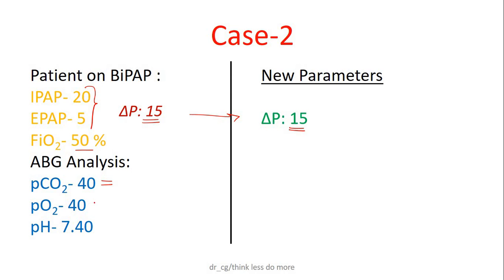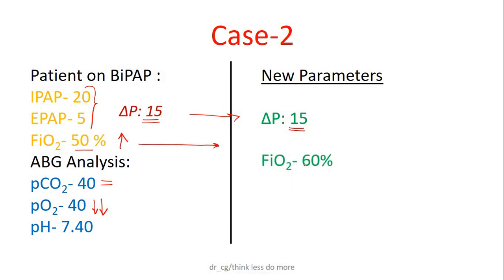Now see PO2 level — here it is 40, meaning it is very low. So we can increase our FiO2 to 60% from 50%. New FiO2 is 60% and there is no change in EPAP. So new required pressure difference is 15 — no change in IPAP and EPAP.